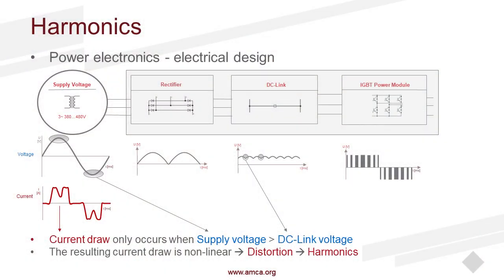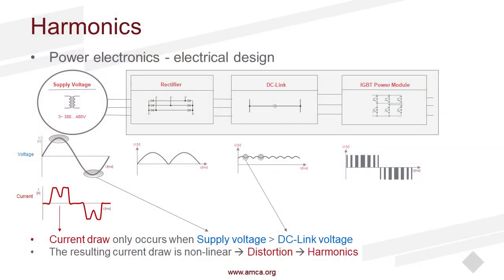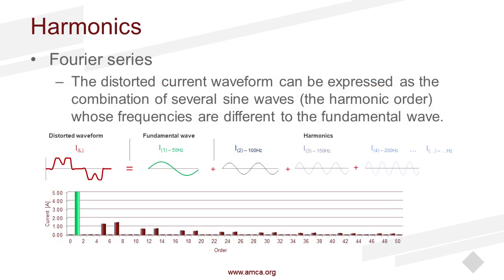Then you take your DC voltage, and now it's going into your IGBT power module. This is sending out a PWM, pulse width modulation signal, and now you're converting it back into a similar AC sinusoidal wave. And so when you're doing this, you're changing your voltage, and with that, you see distortion and thus harmonics. With your current distortion, you can then start to see distortion within your voltage, and that's when you start to have problems.